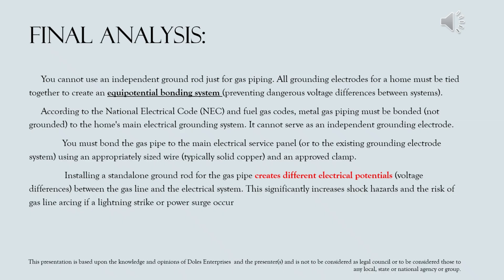According to the NEC and the fuel gas codes, metal gas piping must be bonded. That's what we have to live with. And it's got to be bonded to the home's main electrical grounding system. It cannot be an independent grounding electrode, which is what you see in this picture. You must bond the gas piping to the main electrical panel or to the existing grounding electrode system using an appropriate size wire, typically solid copper, and an approved clamp.